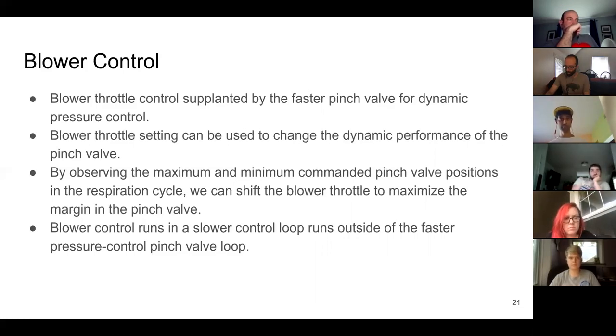What I propose here is that we have the system watch the operating envelope of the pinch valve, or whichever proportional valve we use. It watches that operational envelope and keeps it within the most effective dynamic range of the actuator. So we can slide that back and forth in a slower loop than the pressure response loop, which is the main real-time control of the ventilator. That's something we can look at. It's not something we need to focus on right now, but it's another knob we can turn to gain additional performance.